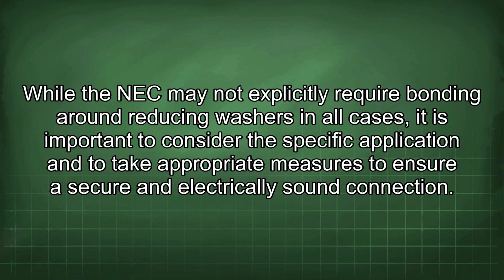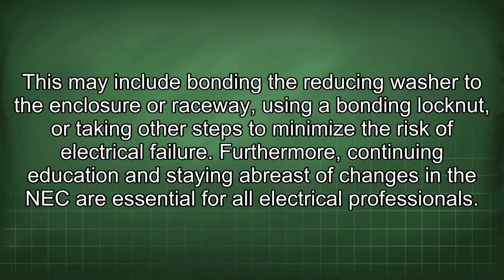While the NEC may not explicitly require bonding around reducing washers in all cases, it is important to consider the specific application and to take appropriate measures to ensure a secure and electrically sound connection. This may include bonding the reducing washer to the enclosure or raceway, using a bonding lock nut, or taking other steps to minimize the risk of electrical failure.